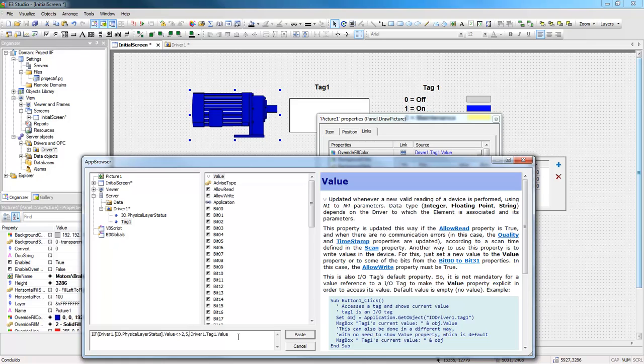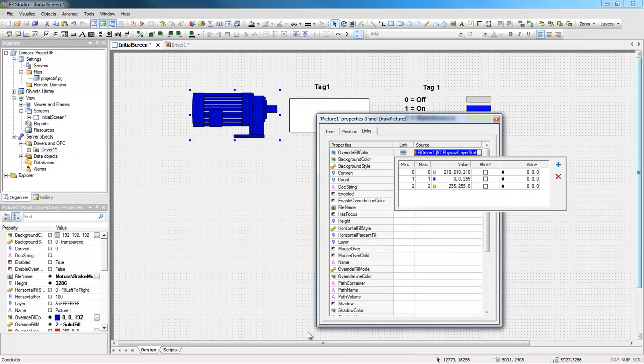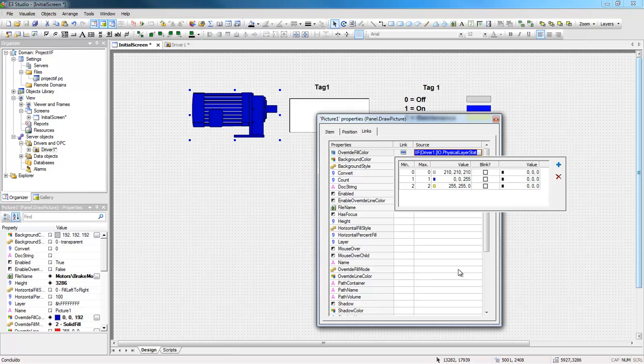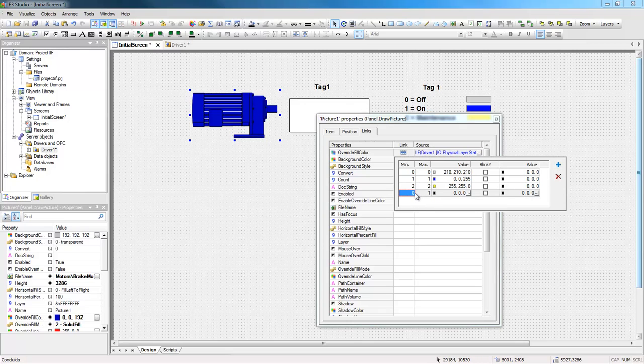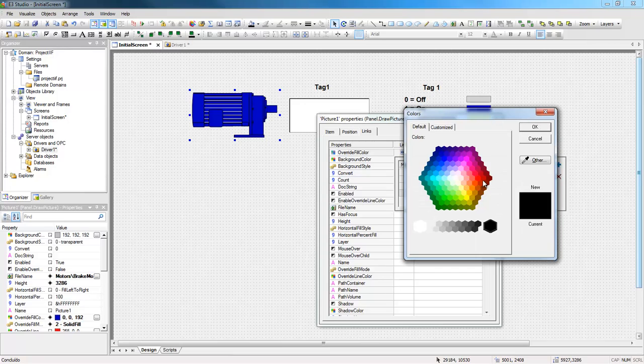If the value in the PhysicalLayerStatus is 2, I will use the values returned by the tag. That is, when I paste this onto the link, if the value at PhysicalLayerStatus is not 2, which means communication fail, the link will return 5. I will put the value in red and blink it with yellow to show communication fail.